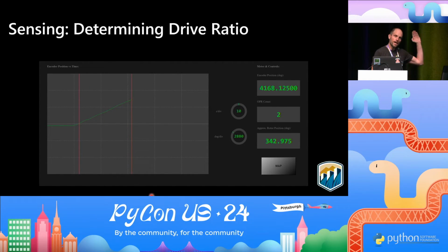As soon as I hit the first red line, I say okay, my rotation started. Now I'm going to track that rotary encoder until I see the second red line. And I saw 4,168.125 degrees - that's how much the encoder turned for one revolution of the rotor. So I know the drive ratio: for every 360 degrees the rotor turns, the encoder on this particular machine turns 4,168.125 degrees. There's my drive ratio.